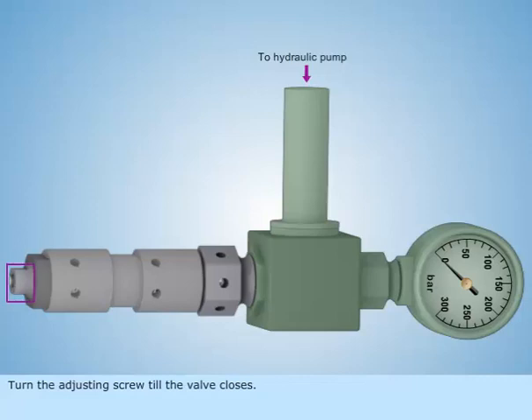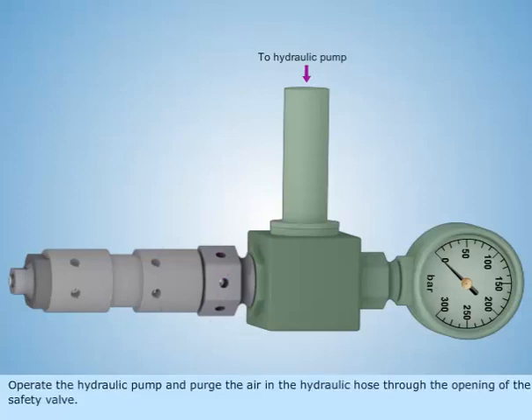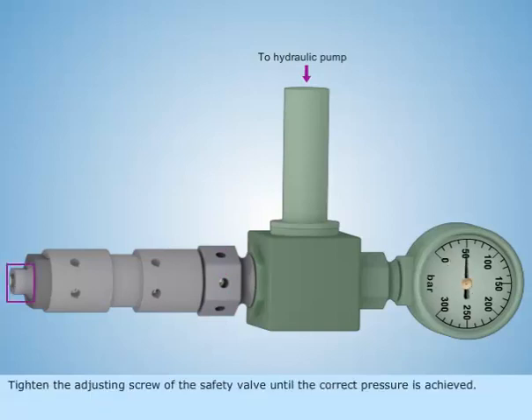Turn the adjusting screw till the valve closes. Operate the hydraulic pump and purge the air in the hydraulic hose through the opening of the safety valve. Tighten the adjusting screw of the safety valve until the correct pressure is achieved.